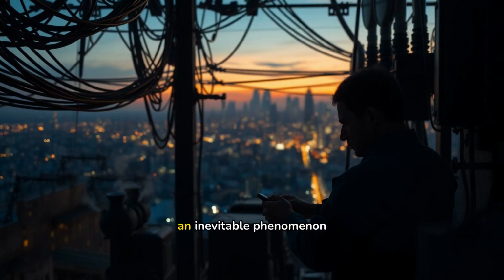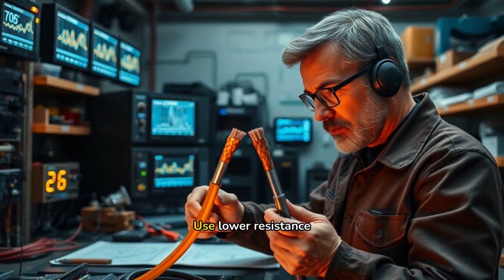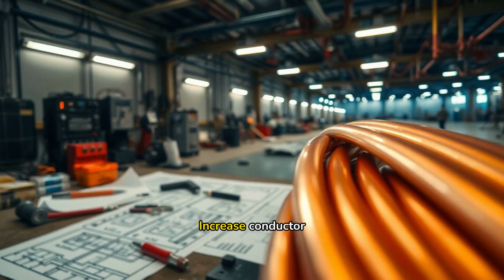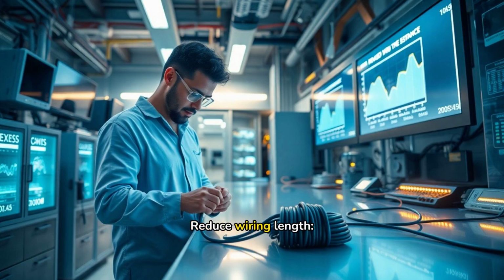Although voltage drop is an inevitable phenomenon in any electrical system, there are several ways to reduce it and minimize its impact. Use lower resistance conductors. Using copper wires instead of aluminum is an effective way to reduce voltage drop due to the lower resistance of copper. Increase conductor thickness. A thicker conductor offers less resistance, which helps reduce voltage drop in long installations or high current consumption. Reduce wiring length. Whenever possible, it is advisable to minimize the length of cables to reduce the overall resistance of the system.